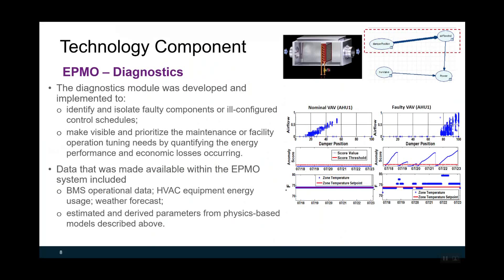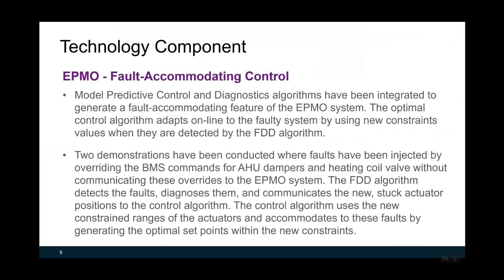For a faulty VAV box, we can see the room temperature was not maintained. At the same time, our algorithms were able to pick up this anomaly with a high anomaly score. Data made available within the EPMO system includes building management system operation data, HVAC equipment energy usage, and weather forecasting. Both estimated and derived parameters from physical-based models described in the previous slides are also available within the EPMO system.